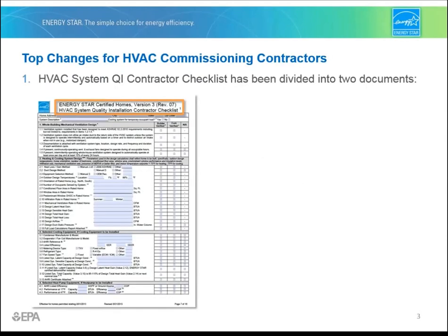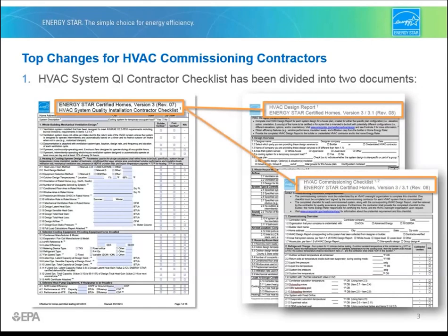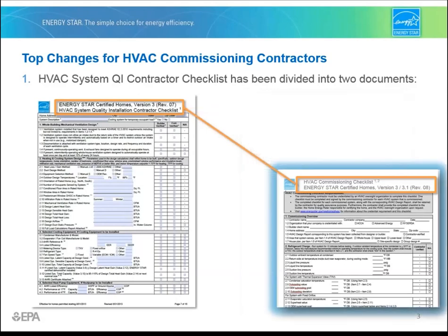First, let's discuss the top changes you need to be made aware of in Revision 8 as an HVAC commissioning contractor. Number one, the HVAC system QI contractor checklist that you used to complete has been split into two documents: the HVAC design report and the HVAC commissioning checklist. As an HVAC commissioning contractor, your job is to complete the HVAC commissioning checklist.